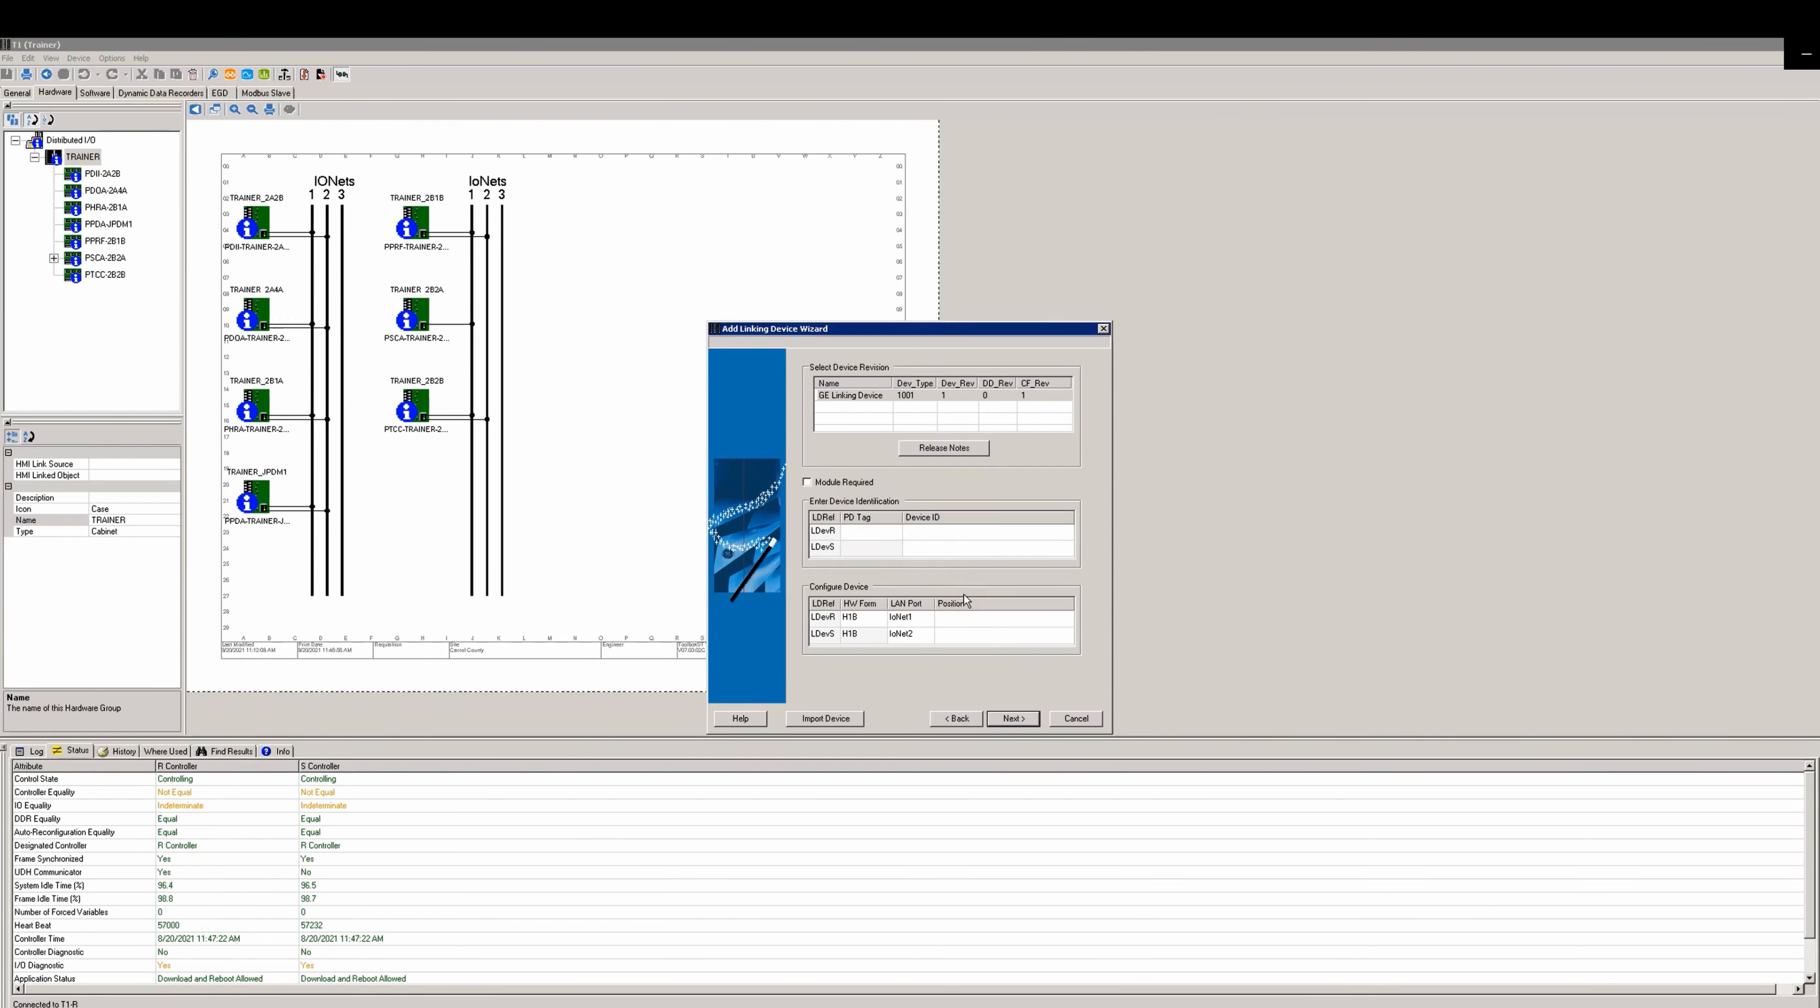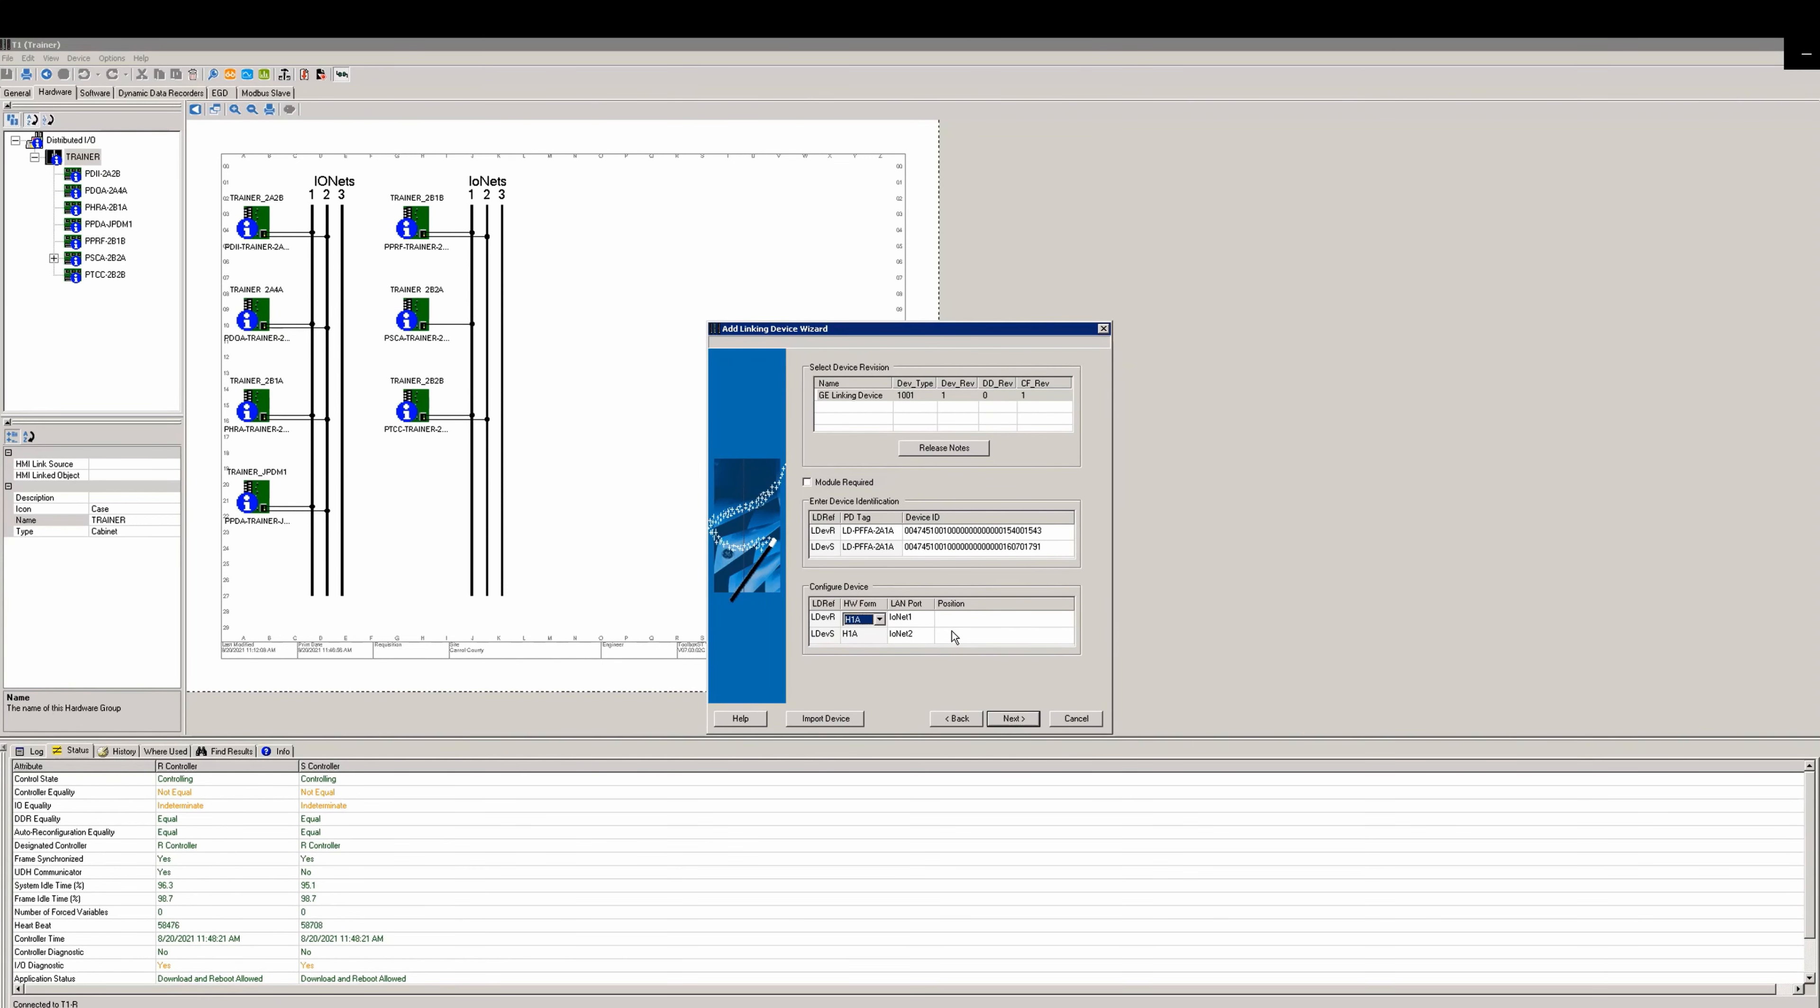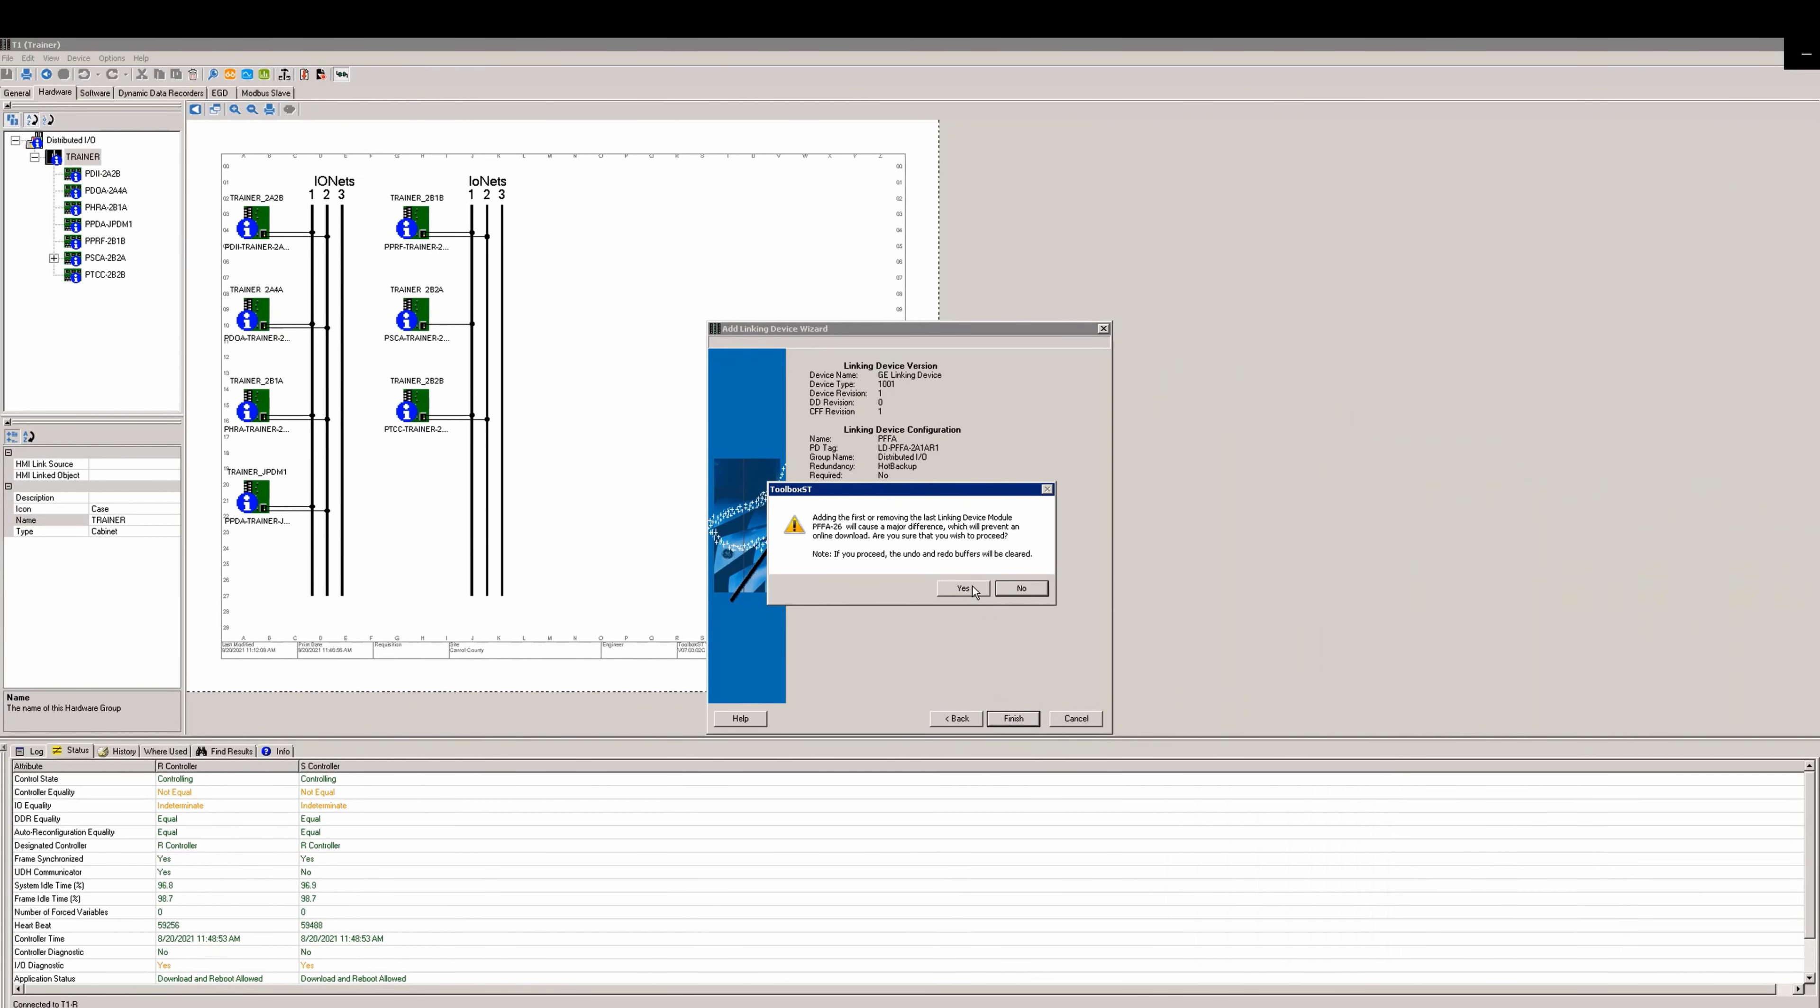We're deselecting module required to ease in the download. Now assign a PD tag - we're going to use 2A 1A because that's where it's located in the cabinet. In the next field for device ID, select the browse button and select the ID for the pack at the first location. Select browse again and select a second ID. Next select the correct hardware form of the pack, type in the position and the rack, select next and then finish.